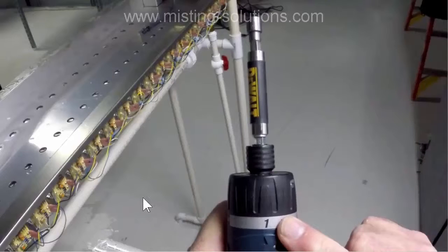But you can't tighten these transducers very much. They don't need to be tightened very much because it's just in an open bath of water. I'll show you here in a little while the O-ring and actual rubber gasket that's used to seal this transducer nebulizer to the bottom of the plate.